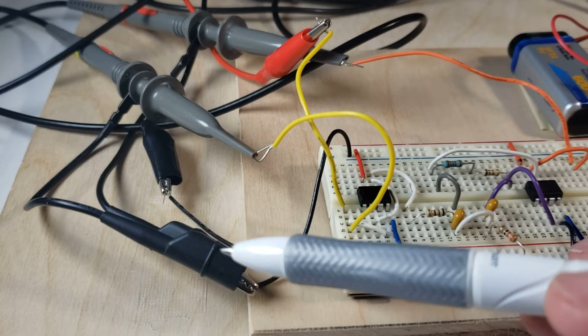One thing you can do when troubleshooting is check that your generator input, say set to 2 kilohertz at 200 millivolts, actually shows up correctly on the generator's screen. It seems like I do have that right now.